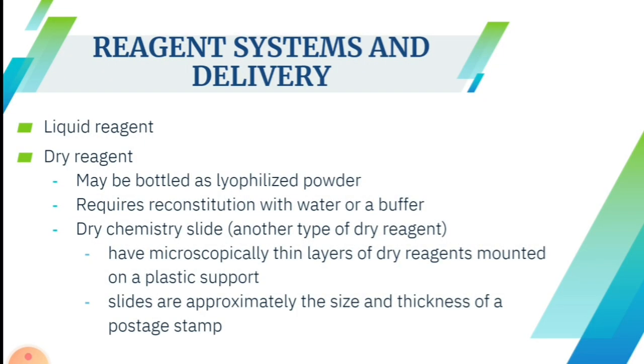So reagents may be classified as liquid or dry systems for use with automated analyzers. Liquid reagents may be purchased in bulk volume containers or in unit dose packaging as a convenience for stat testing on some analyzers. Dry reagents are packaged in various forms. They may be bottled as lyophilized powder, which requires reconstitution with water or buffer. Unless the manufacturer provides the diluent, the water quality available in the laboratory is important.